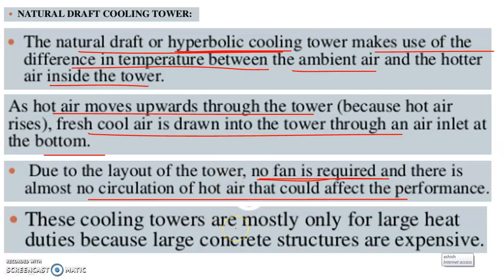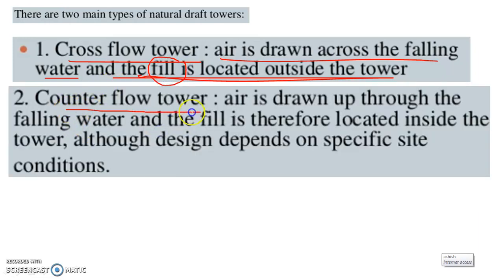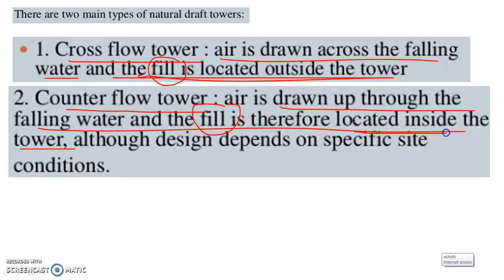These cooling towers are mostly used only for large heat duties because large concrete structures are expensive. There are two types of natural draft cooling towers. Number one is the cross flow cooling tower, where air is drawn across the falling water and the fill is located outside the tower. Number two is the counter flow tower, where air is drawn up through the falling water and the fill is located inside the tower.